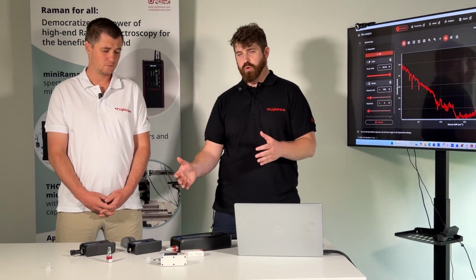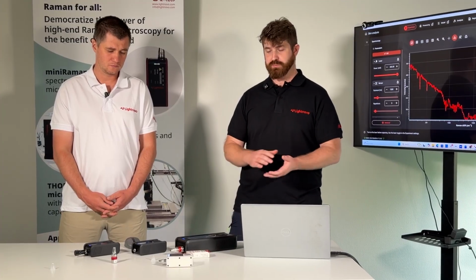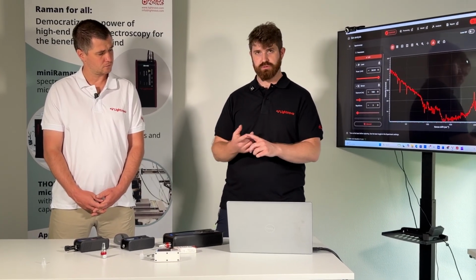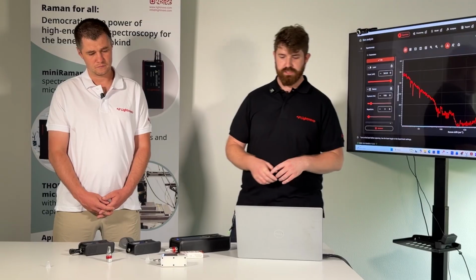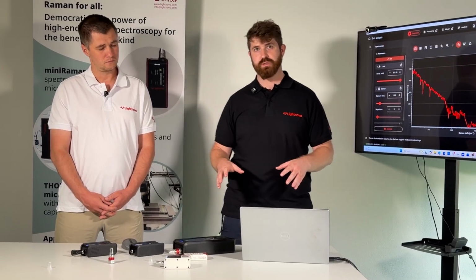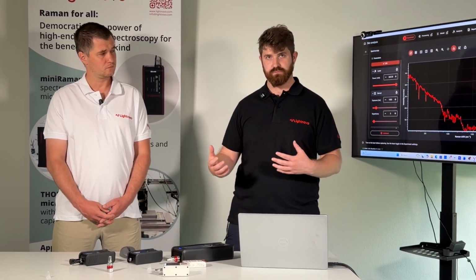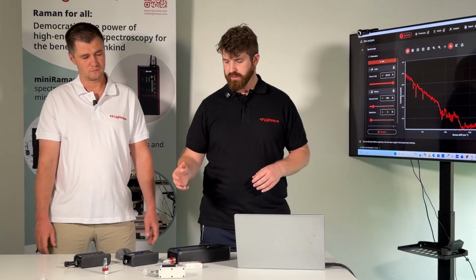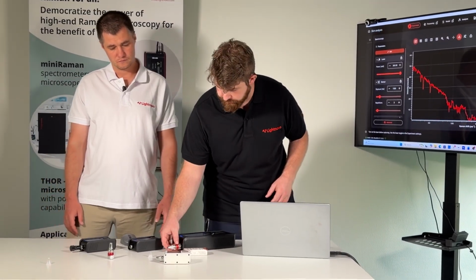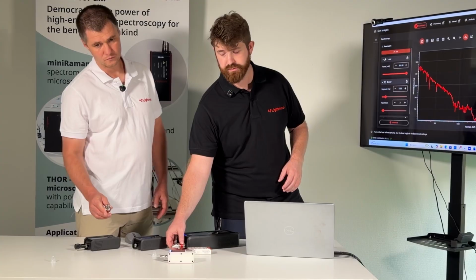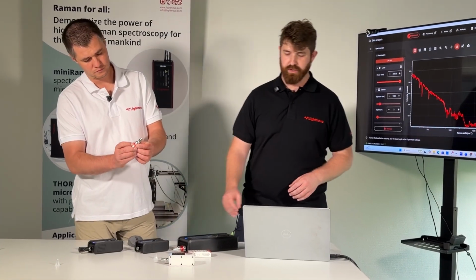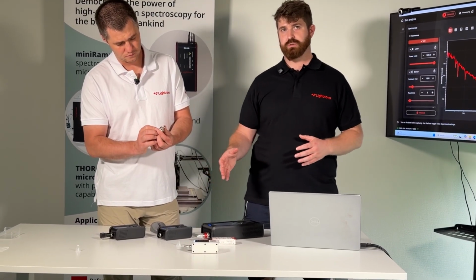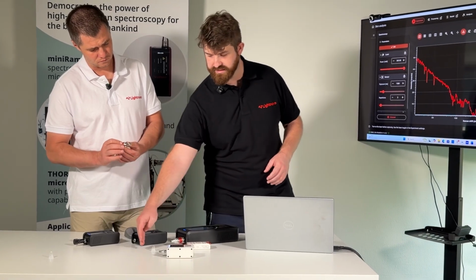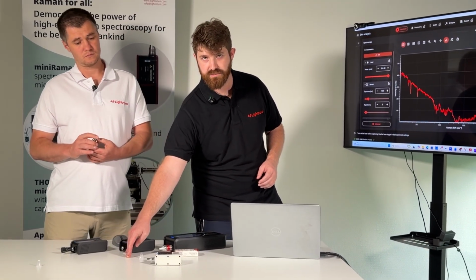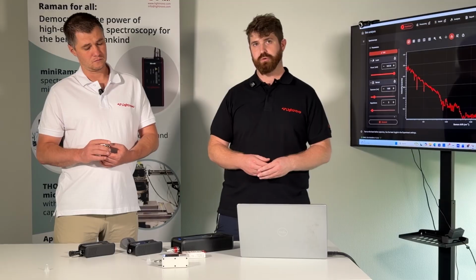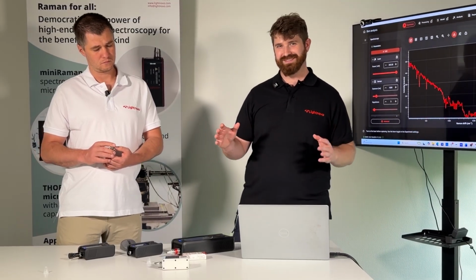So what I'm going to do is I'm just simply going to use my finger for these tests. So we're going to analyze the skin on the tip of my finger. We're going to try and use very similar settings between the two so that we're getting a real comparison of what the results are. This is the variable probe, currently set to 0, so it's focused very, very tight. We've got a very good numerical aperture here, so the laser safety distance is about 13 centimeters from the end of the probe, so you are perfectly safe.